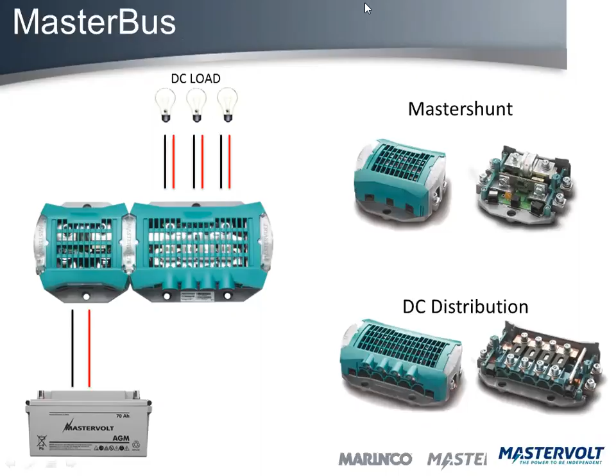Does the master shunt have overcurrent protection? Yes. In the master shunt itself, there's a T-class 500 amp fuse, and that's actually circuit protection. So if you want to comply with ABYC and stay within the 7-inch range or 72-inch range, you can use that shunt close enough to the battery so you don't have to have a separate inline fuse for the system. These shunts are 500 amps each, but you can parallel up to 4, and then electronically in the network you can combine them so you will see one state of charge, one voltage, one amps, and one time remaining.